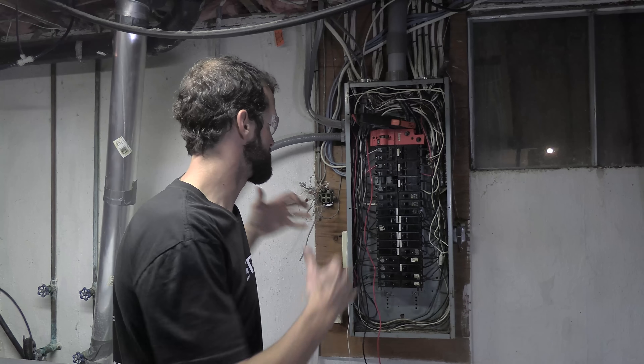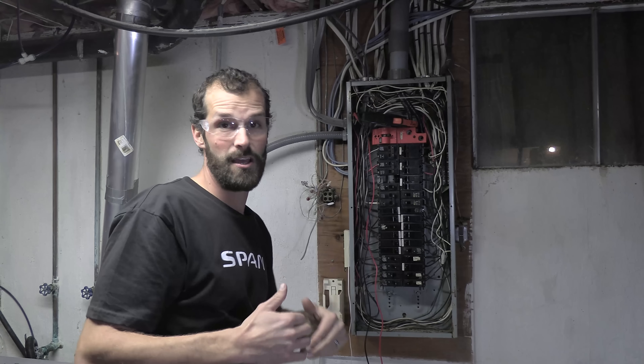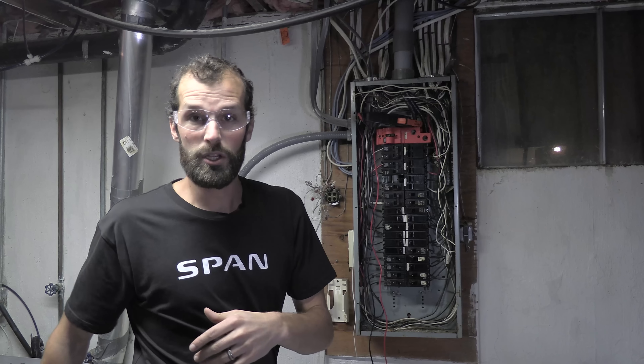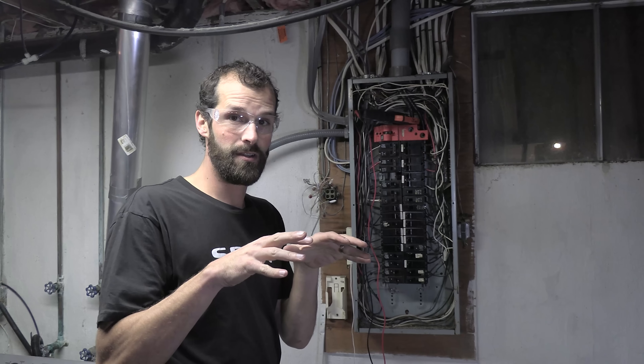What I might see is the accumulation of heat, the buildup of heat. What I might see is arcing. What I might hear is a sizzling or fizzling sound. And I'm going to see the ampacity jump because this is about a 20 to 25 amp load. That's going to allow the situation to rear its ugly head.